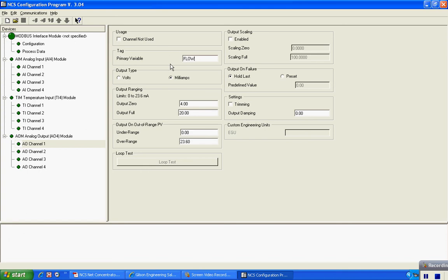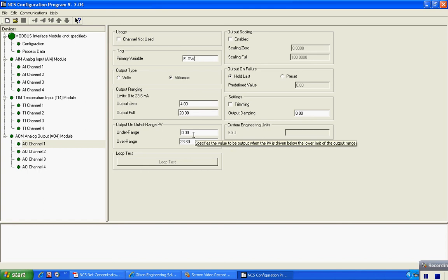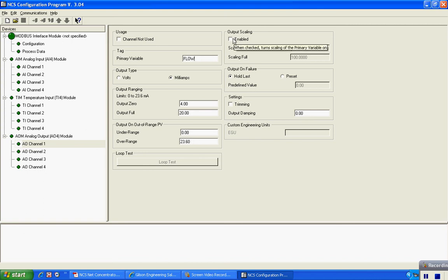We'll call this flow. We have an output of 4 to 20 that we would like to take to another device, and the output on out of range value, you can configure this so that it will go either to zero, or in this case over range will go to 23.6 milliamps. Output scaling is available. We'll enable that and we're going to configure this for a 0 to 250 GPM flow signal.